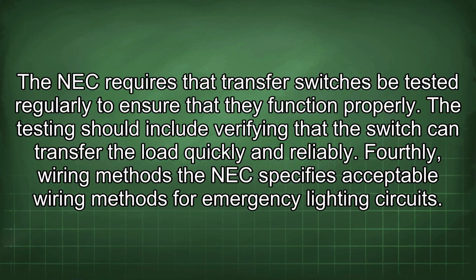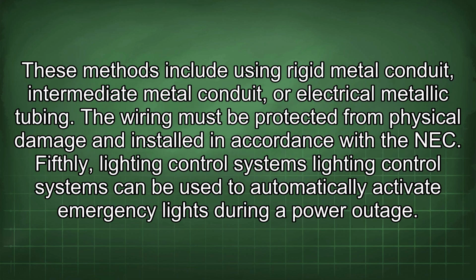Fourthly, wiring methods. The NEC specifies acceptable wiring methods for emergency lighting circuits. These methods include using rigid metal conduit, intermediate metal conduit, or electrical metallic tubing. The wiring must be protected from physical damage and installed in accordance with the NEC.